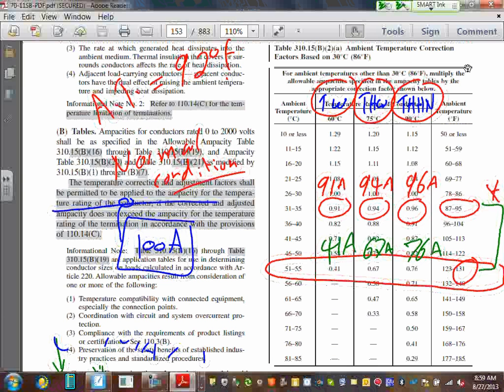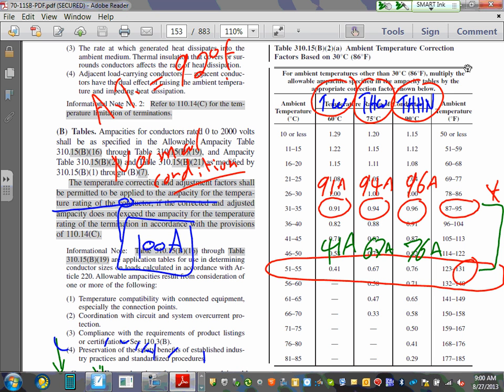76. That's the concept of operation of the derating temperature. That's why derating is so powerful. In Minnesota, when we do ambient temperature, we take 92 degree Fahrenheit. That's what we size based on. These ambient temperatures are decided by ASHRAE, the mechanical guys. So for us, it's 92 degree Fahrenheit. It's not a maximum ambient temperature. Like today, 95 or 100 in Minnesota, that's not a maximum. They average over the years and come up with a statistical value. That's how they come up with the ambient temperature for the city that you're in.